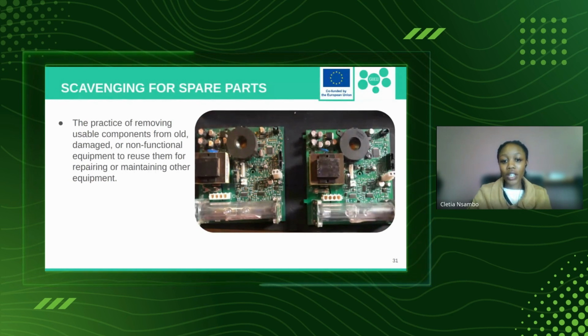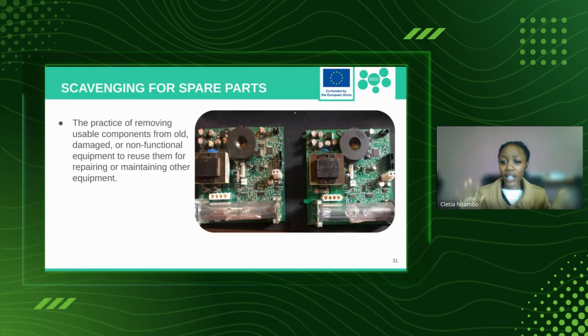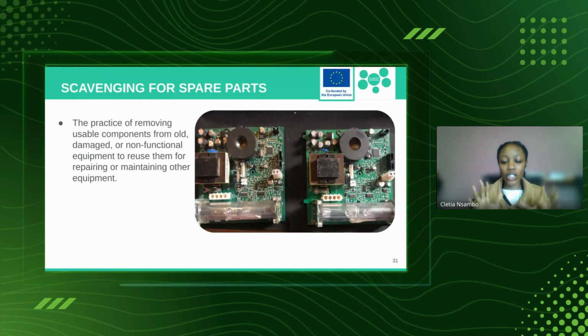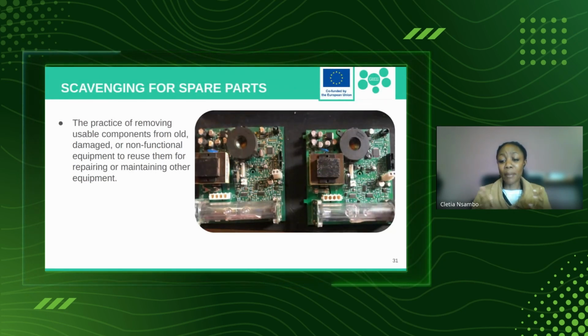So ideally, let's say you have 10 oxygen concentrators that are not working. You can take a part from one and replace it in another. If you do this, instead of having 10 non-functional oxygen concentrators, after scavenging for spare parts, you can end up with maybe 5 or 6 functional ones. That's better than having all of them broken down. This usually works for compressors and concentrators of the same brand or model.